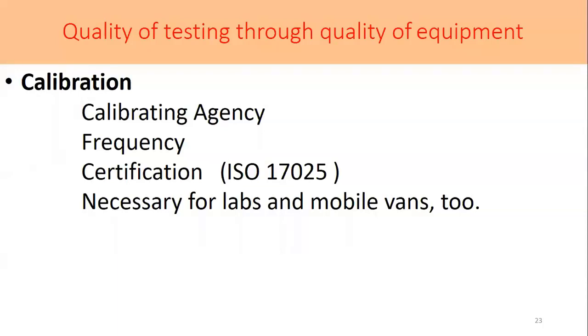They say we have calibrated the equipment, that too with certification from an ISO certified testing agency. And if you ask them when they last obtained the calibration certificate, they say it was some four years before. So that is not sufficient. Whether you are maintaining the proper frequency of calibration matters a lot.